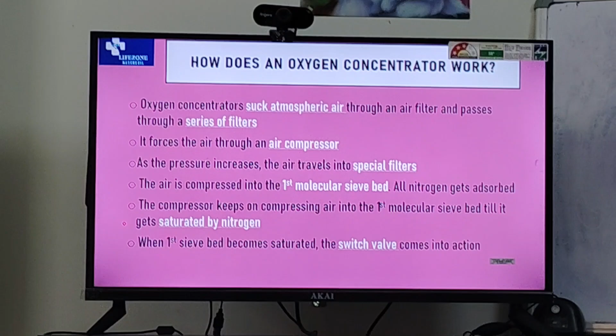Now let us see the principle which is applied. We know that this is the way it looks inside the oxygen concentrator. There are filters and the air is sucked into the concentrator through the filter. Then it passes through the compressor, and it forces the air through, and as the pressure increases, the air travels through different filters. The air is compressed with the first molecular sieve.